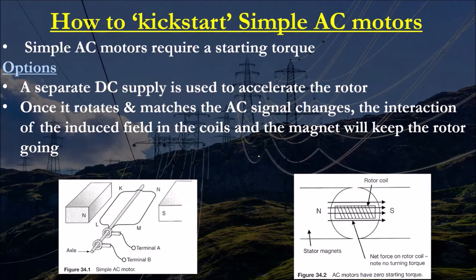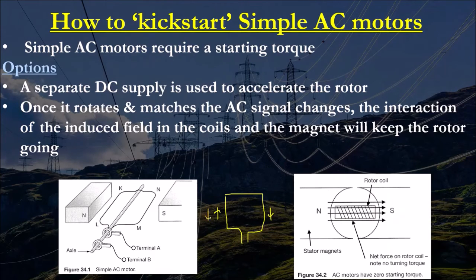Essentially, if you have a motor and the current is moving in here and then moves out, and then the next rotation goes in the opposite direction, what tends to happen at the start, if you're just left with simple AC, is that our AC current doesn't have a strong enough starting torque. So it kind of vibrates on itself. It doesn't have a strong enough starting torque to start rotating.